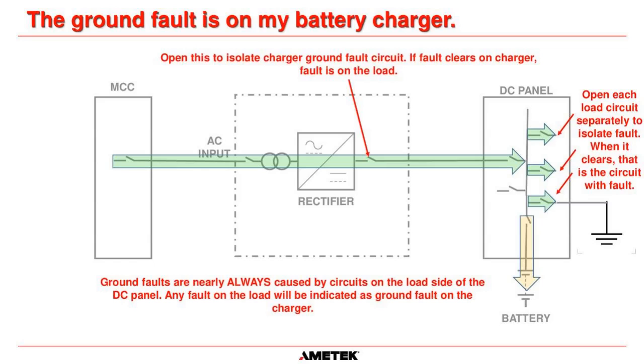It is much more likely that it's going to be a load circuit, and it could be in the battery if you have a really poorly maintained battery that has acid leaking all over the place. Then acid is conductive, and it can track down from a post down to the frame of the battery rack and cause a fault as well. So the easiest thing to do there is open the battery disconnect, and if the lamp goes off, then you know it's a problem with the battery.